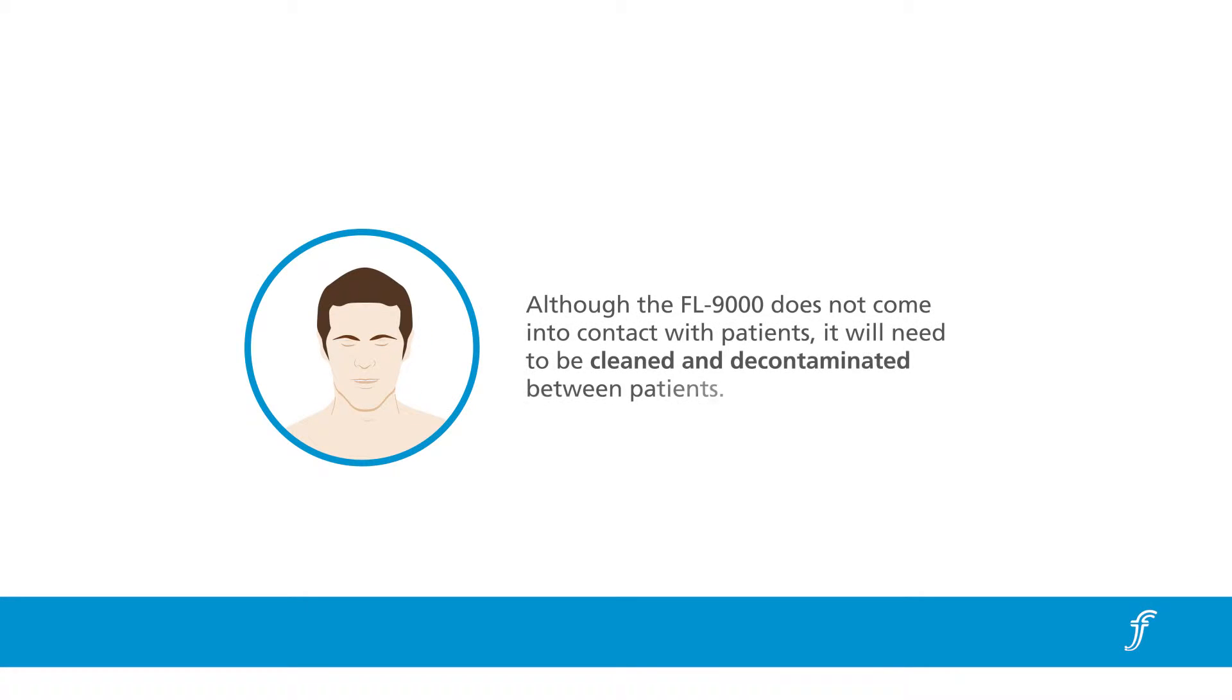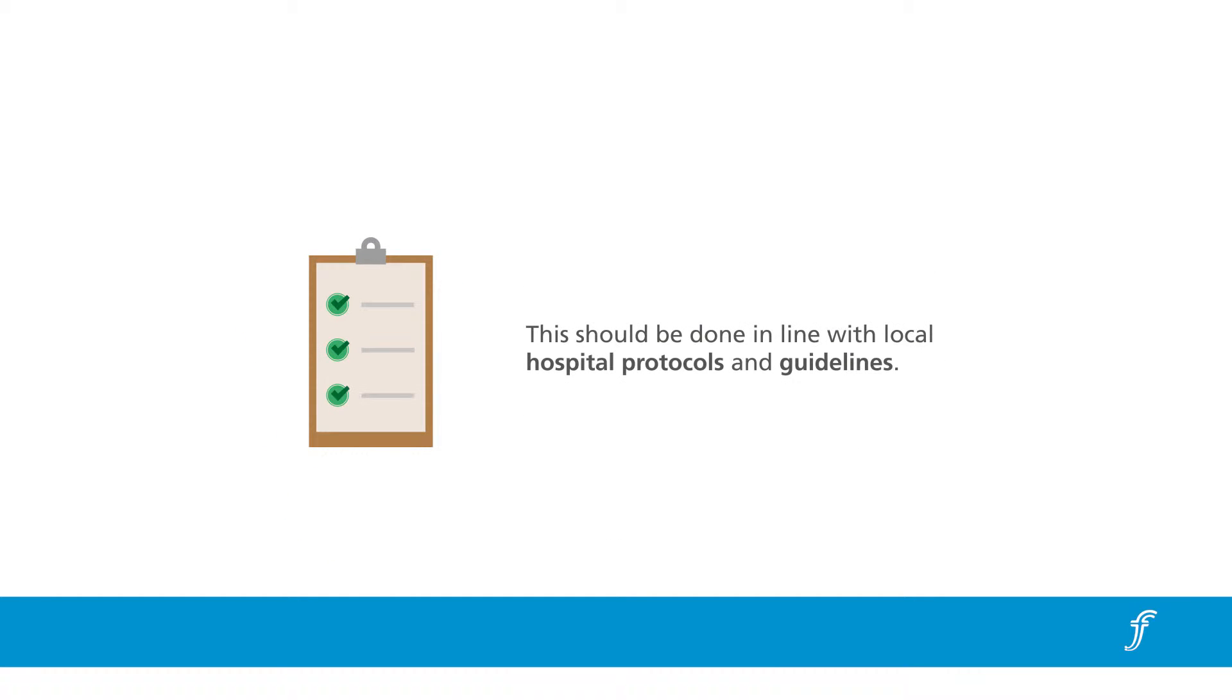Although the FL9000 does not come into contact with patients, it will need to be cleaned and decontaminated between patients. This should be done in line with local hospital protocols and guidelines.